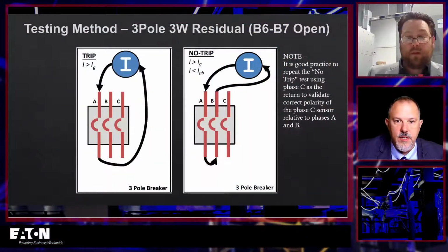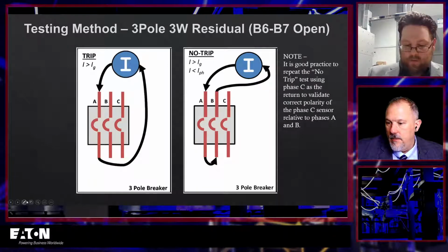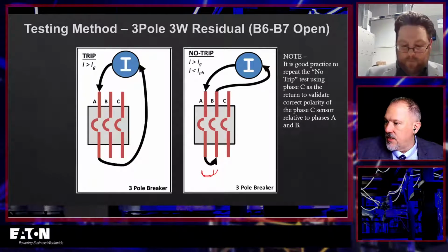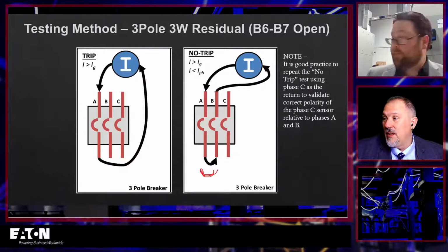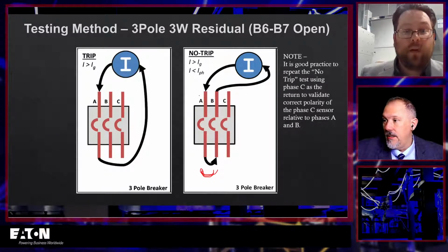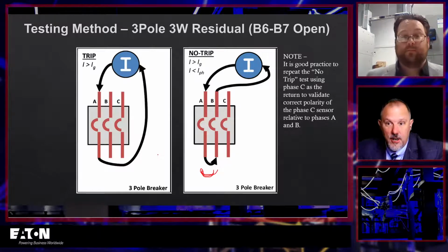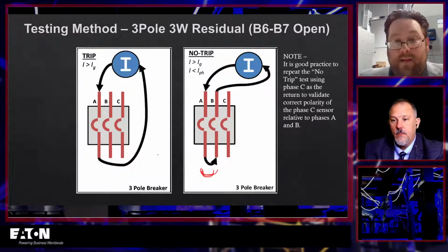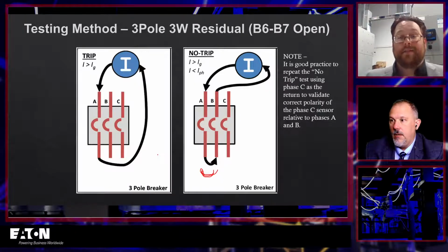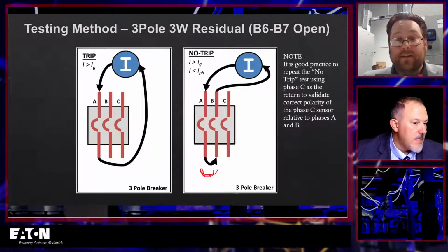What else? Oh yeah, and this is again to reinforce that. You've got your A and B. You're going to be doing A and B. That shouldn't trip either, right? Yeah, no. That's a no trip test. So you've also got to do the relationship with each other, not just the neutral. That's a really good point. And that's because this is a residual connection, right? In residual, we have to be able to sum up the sensors or the CTs that we have available to us. It has to equal zero. So yeah, no trip in this instance because we don't actually have a neutral CT. That's exactly right.